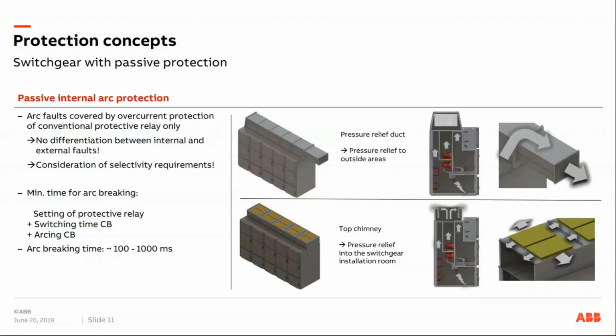do not have Is-limiters, or where there is no differentiation between internal and external faults possible. The arc faults are covered by the overcurrent protection of conventional protection relays.